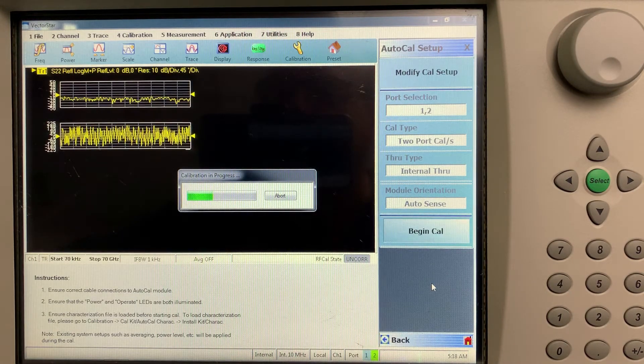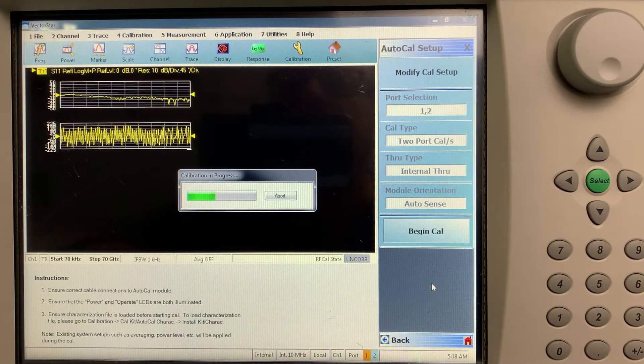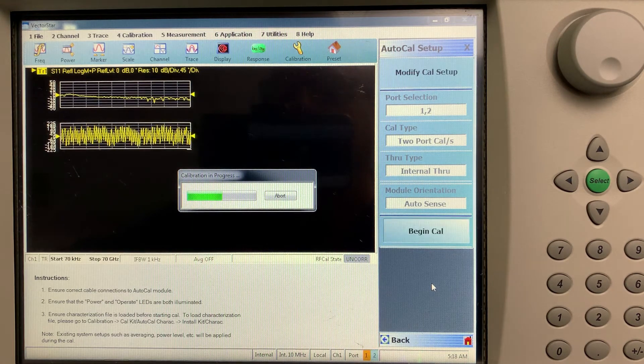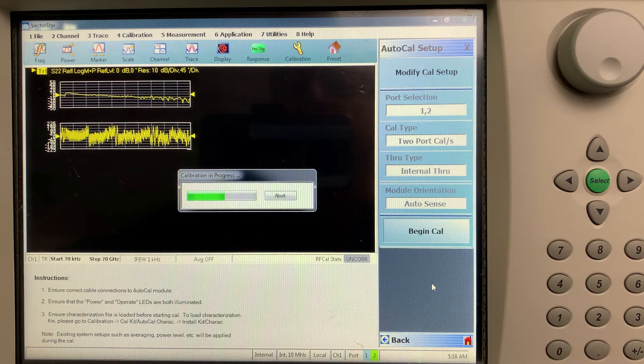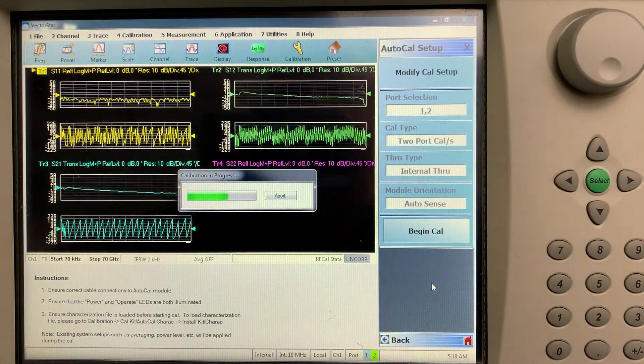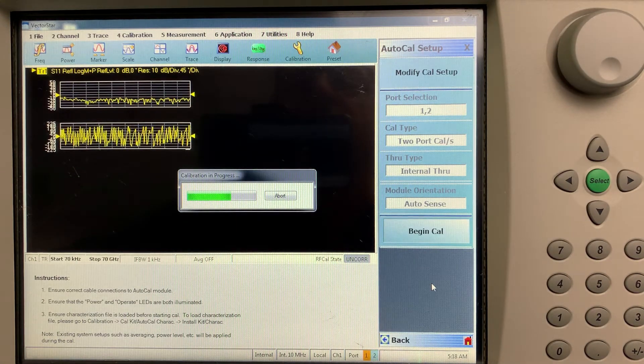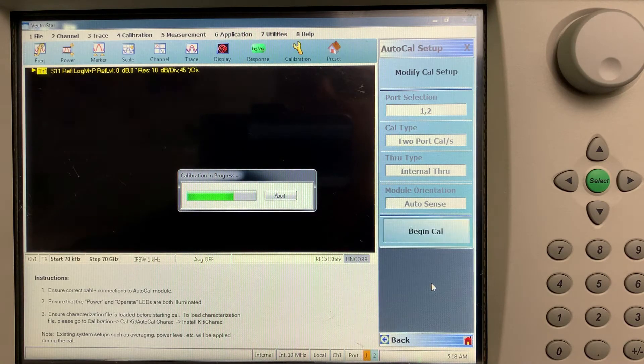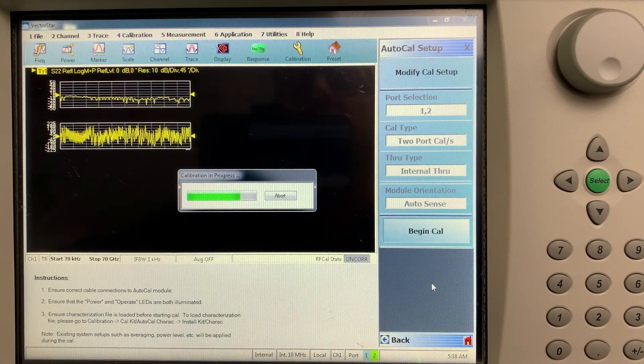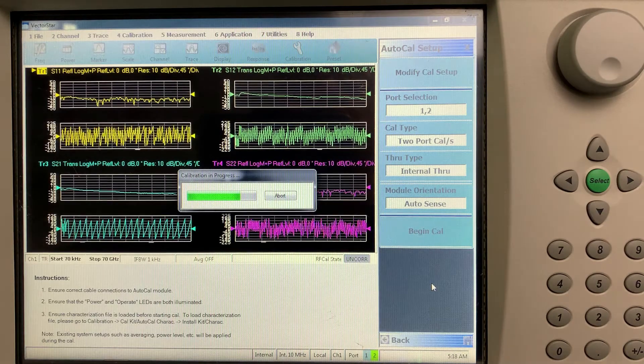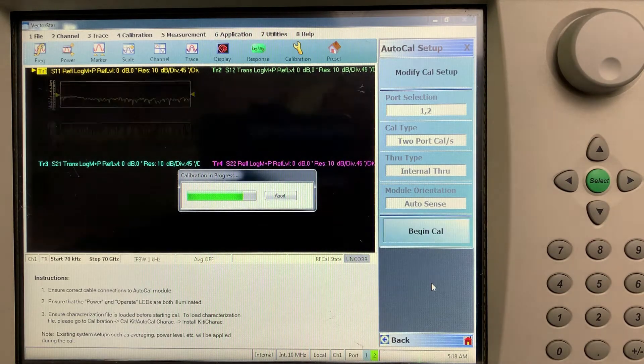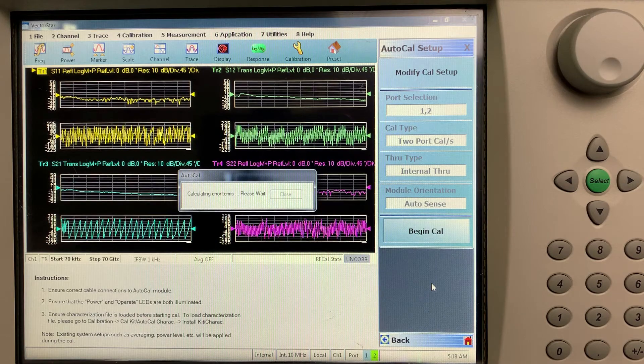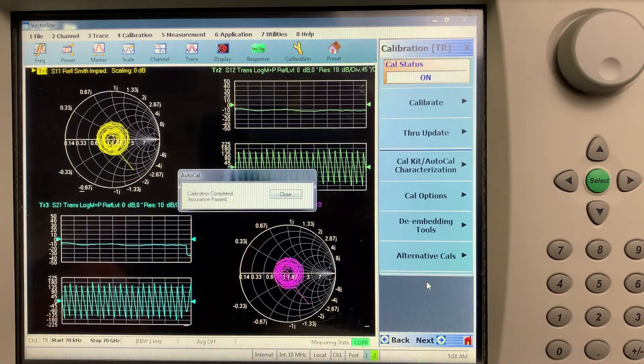And at the end, it'll give an assurance pass. So there's a self-check mechanism inside the Auto-Cal module to say, OK, the calibration is good. I've measured myself inside my internal through. Everything's OK and we're ready to go. So just finishing up now and you'll see it'll pass. There we go. It's done the assurance.